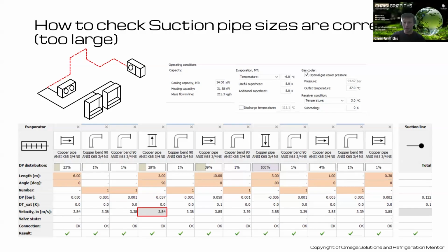In terms of a maximum height on it, it's good practice to put an additional trap in. Generally, I always did 6 meters. Some people think that's probably slightly too much. That's 20 feet. CO₂ is very good at transporting oil, though. That's the important thing to consider there.